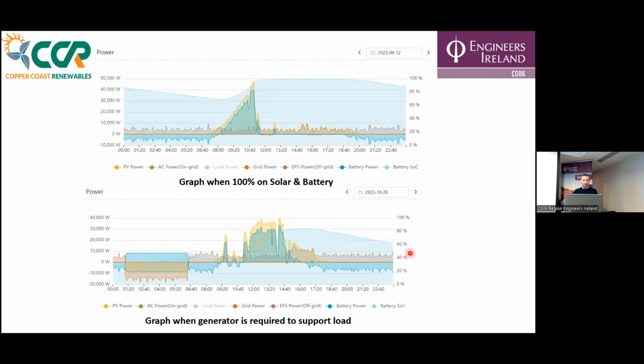So to run through, this blue line here is the batteries, and it runs just like that. So what that means is here you can see at midnight she's running on the batteries until about 1:20. Now the battery state of charge percentage is shown over here, and that's your 20% line. If you come over here, you can see the batteries are just off 20%, or probably just hitting 20%.